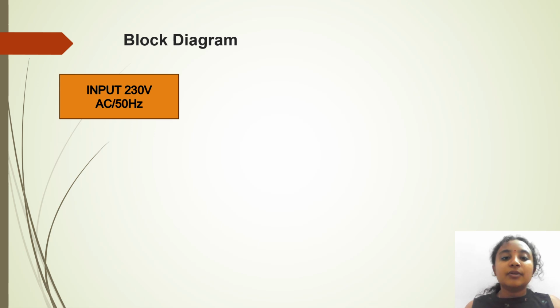In this slide, we discuss the block diagram of the ozone leak monitor. An ozone leak monitor is a device designed to detect and measure the leakage of ozone gas, typically used in industrial settings where ozone is utilized, such as water treatment plants, semiconductor manufacturing companies, and medical facilities. It works by continuously sampling the air for ozone concentration levels.